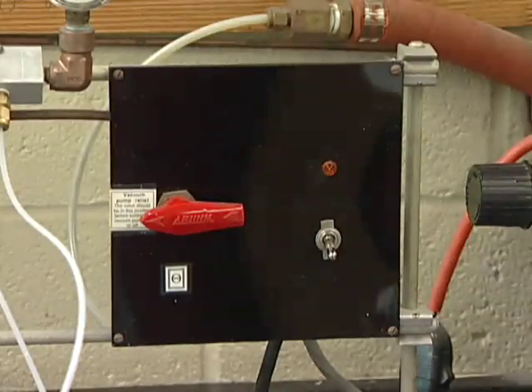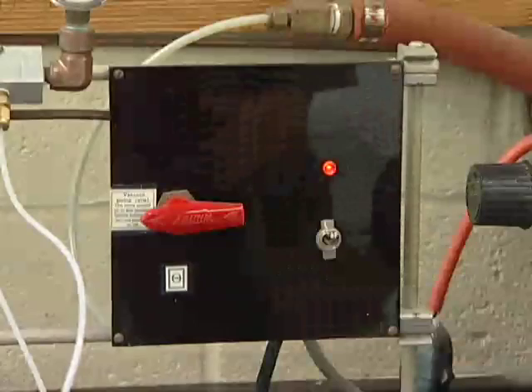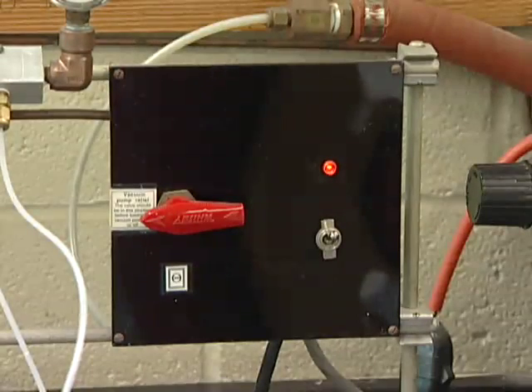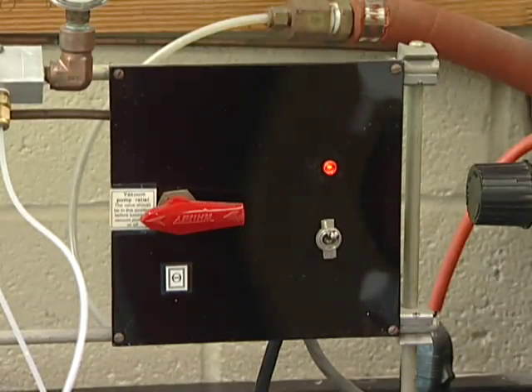At this point, you can turn on the vacuum pump. Whenever you turn on or turn off a vacuum pump, the system should be vented. Close the vacuum relief vent valve after starting the pumps.